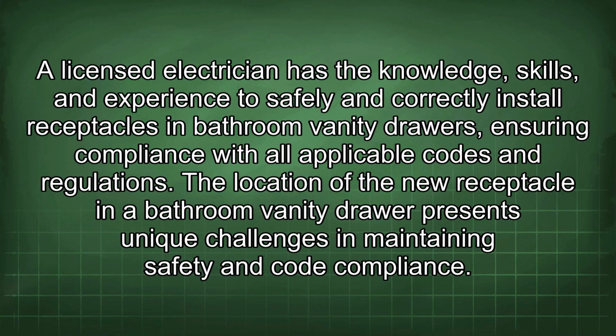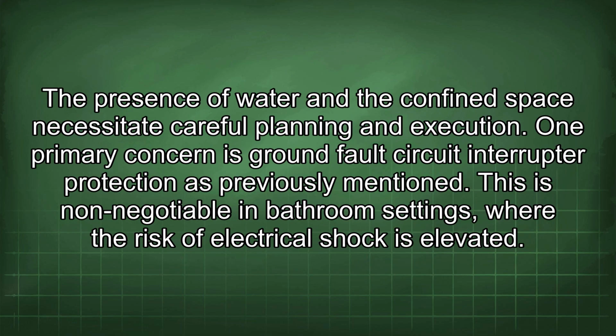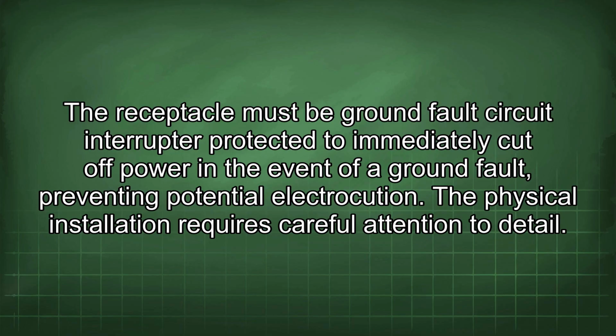The location of the new receptacle in a bathroom vanity drawer presents unique challenges in maintaining safety and code compliance. The presence of water and the confined space necessitate careful planning and execution. One primary concern is ground fault circuit interrupter protection, as previously mentioned. This is non-negotiable in bathroom settings, where the risk of electrical shock is elevated. The receptacle must be ground fault circuit interrupter protected to immediately cut off power in the event of a ground fault, preventing potential electrocution.